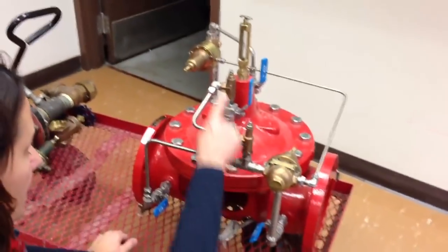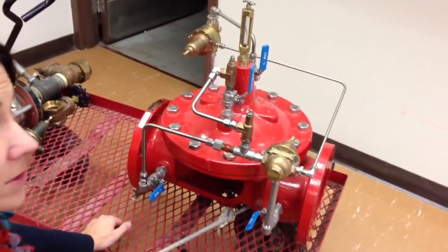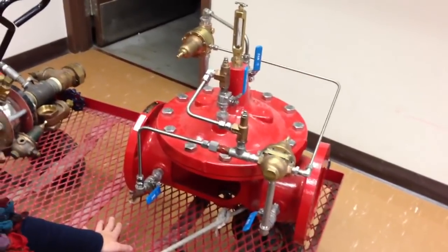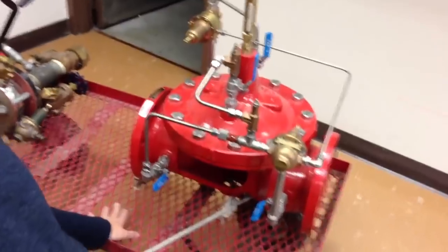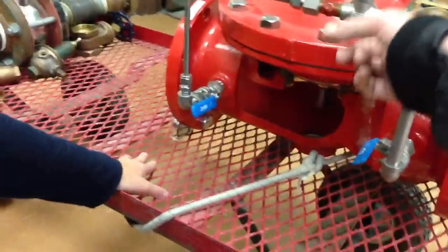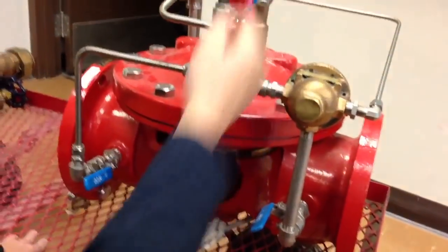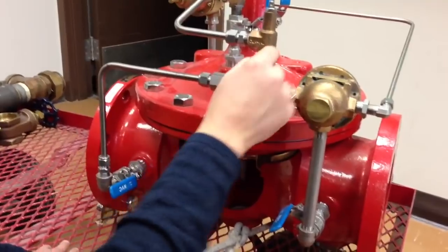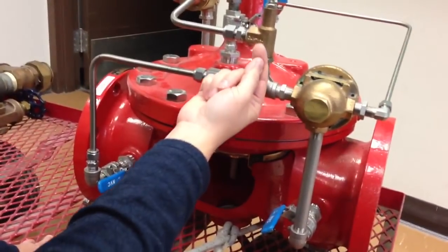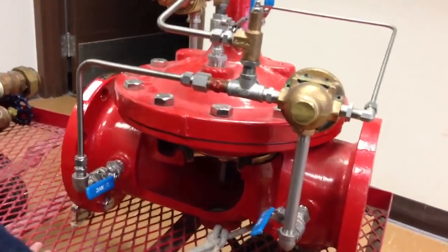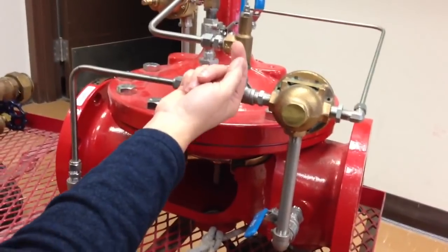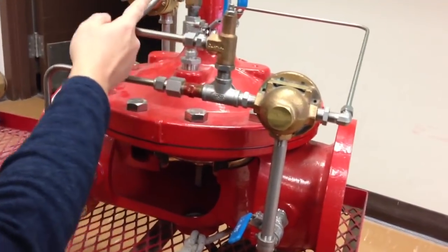Now, is this a needle? That's a needle valve. All of those do is control how quickly this valve opens and how quickly it closes. So is it restricted this way or this way? Now, if you're looking at this, the needle's going down like this. Since the needle's pointing down, the water can slide quite nicely past the needle. So this one is actually not controlling anything in this direction.